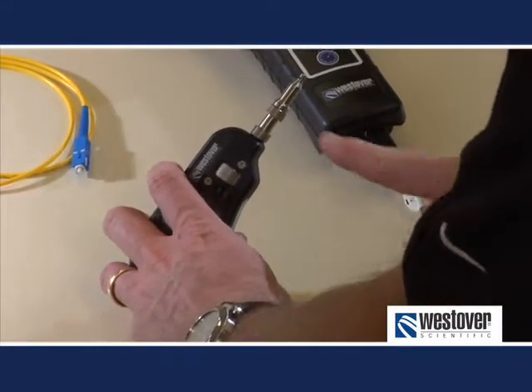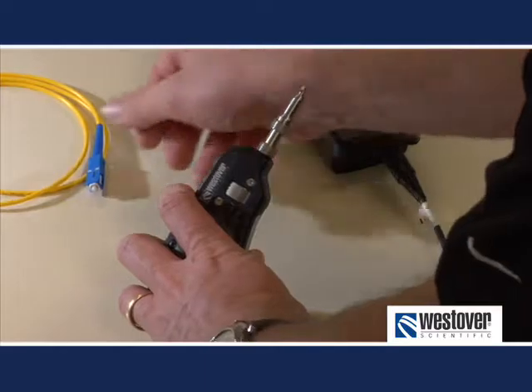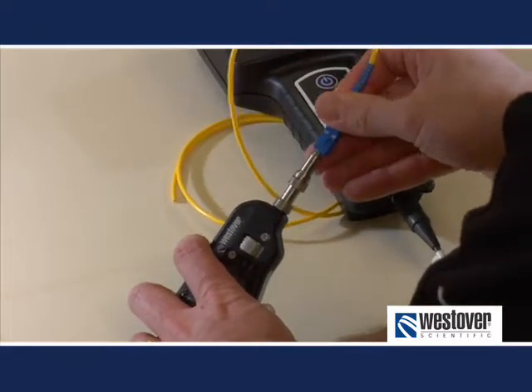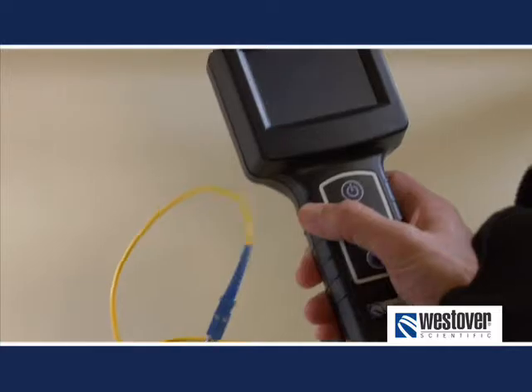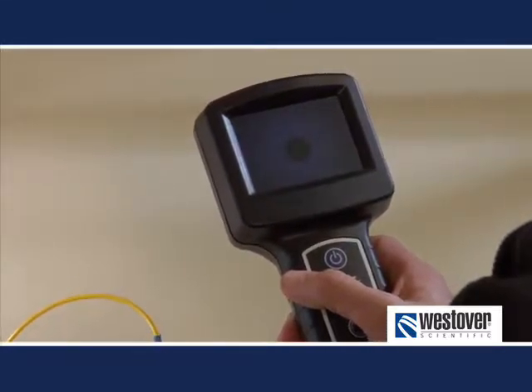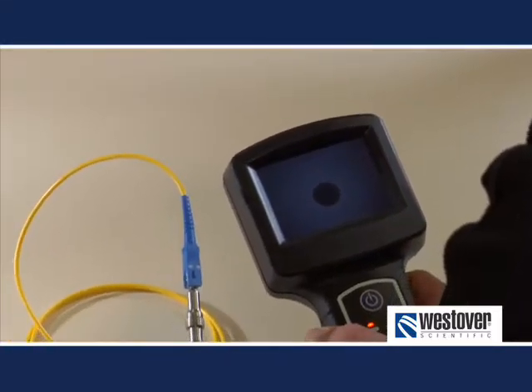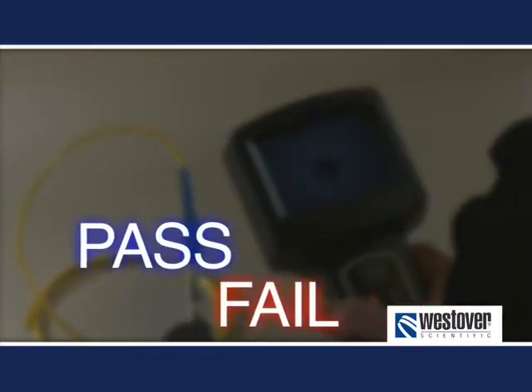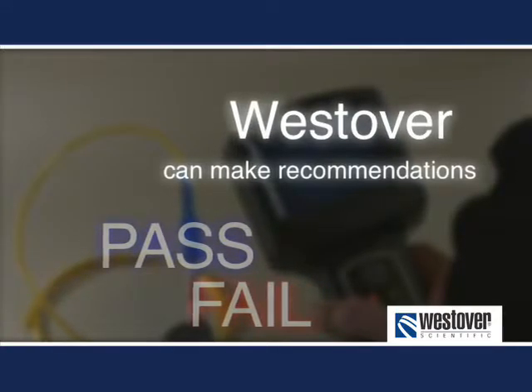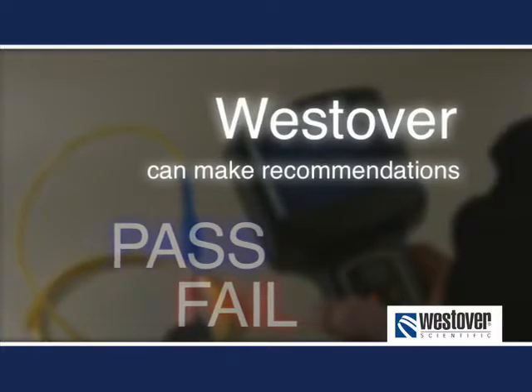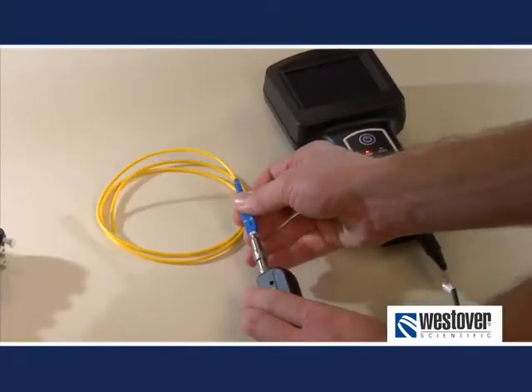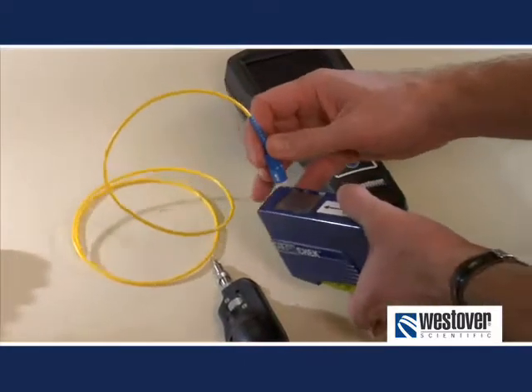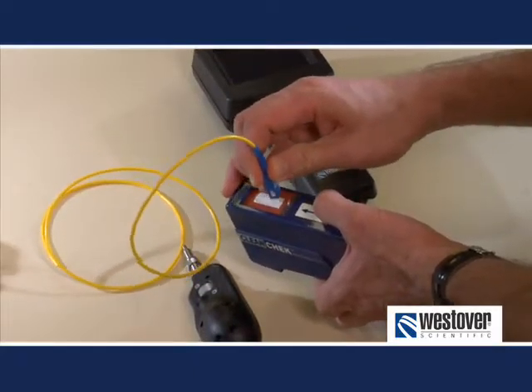Here, we're working with an SC connector. To inspect the male connector, attach the appropriate tip to the probe, insert the connector into the tip, view the image on the display, and focus. Your company may have its own set of pass-fail criteria for determining whether the fiber is sufficiently clean. Alternatively, Westover can provide recommendations. There are some ongoing efforts in standardizing these criteria that may come to market relatively soon. In any case, if the fiber fails for contamination, clean the fiber and repeat the inspection.